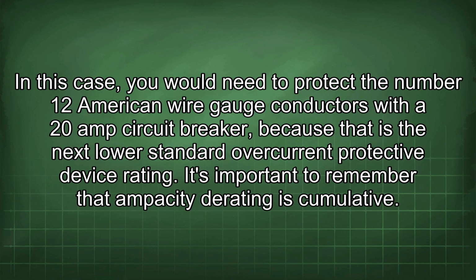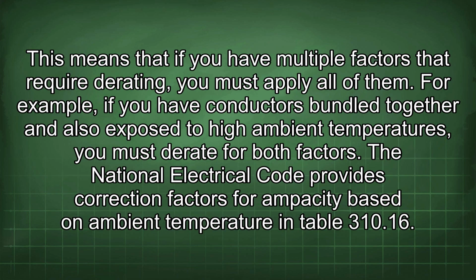In this case, you would need to protect the number 12 American wire gauge conductors with a 20 amp circuit breaker, because that is the next lower standard overcurrent protective device rating. It's important to remember that ampacity derating is cumulative. This means that if you have multiple factors that require derating, you must apply all of them.